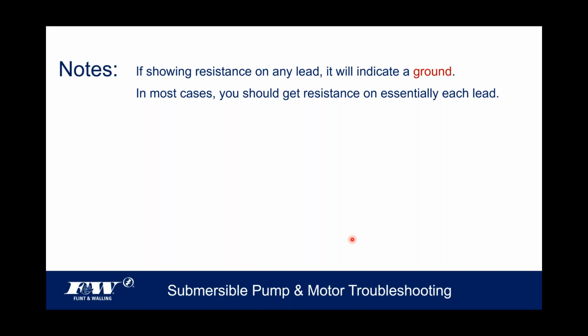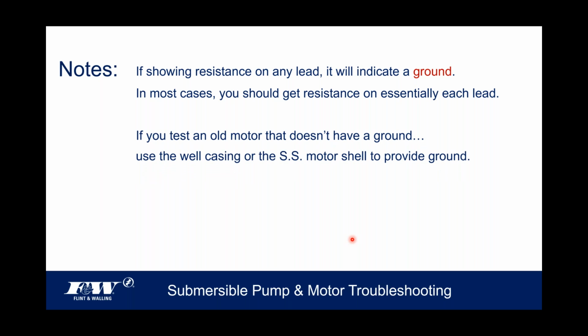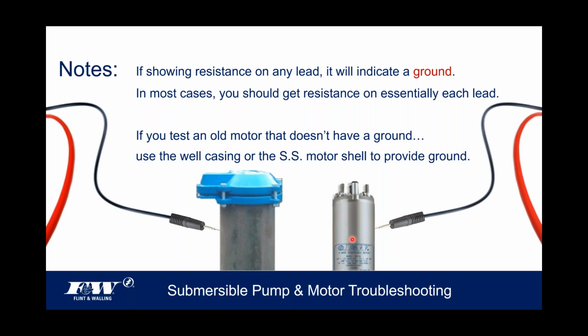And there'll be a day, hopefully, I don't know if it's going to be in my lifetime, but I would think that by now I wouldn't even have to bring this up anymore. But the very first submersible pumps that were manufactured back in the 60s, early 70s, they didn't have a ground wire on them. So when you pulled the pump out of the well, it didn't have that green ground. You, the installer, had to figure out how to ground that water system. So if you happen to pull one of those motors out, we can still test it for ground, but we've got to create a ground since it doesn't have a wire. If it's a steel cased well, you can rub that probe along that casing, get a good solid contact, and you can use that as the ground.